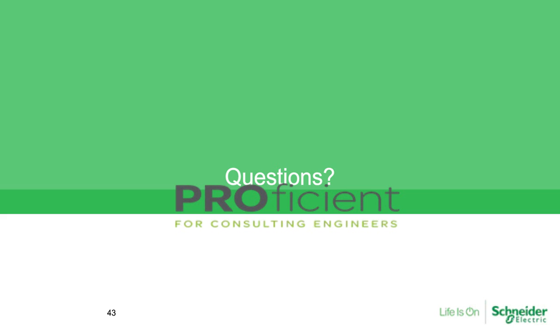Here's another question. How about special cable terminations? Are they required? So again, it depends on the manufacturer. I'll speak mostly towards the Schneider offers, but there's essentially two different types of cable terminations in gas insulated gear. One is, I guess the trade term for it is an intercone connection. It's a connection from Pfisterer. It comes from the high voltage arena. It's typically at 100 kV and above, but they also make it all the way down to 38 kV range. This is a very expensive termination. You have to be specially qualified to not only make the termination on the cable, but install it typically in that switchgear. So installation and just cost of the termination is very high.